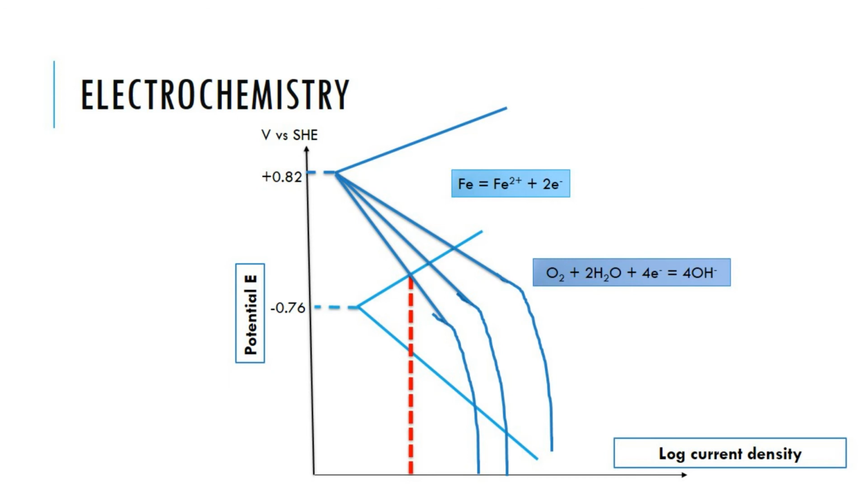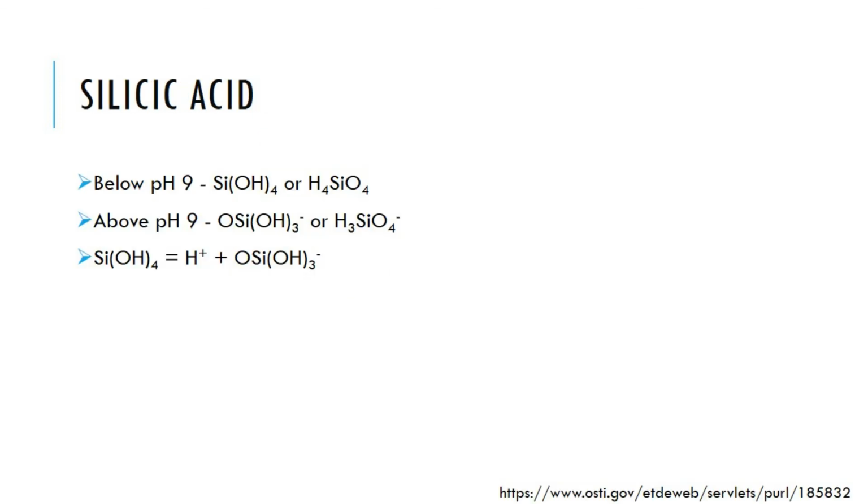Thus, sodium sulfide or the addition of oxygen scavengers can be related to the electrochemistry, and the proper selection of the amount can be done by analyzing the electrochemical nature and formulating the correct contents. Further, there is the concept of silicic acid. Now, this may not seem related to any other parameter, but in fact it is related to the pH. The pH of the boiler in the specifications is 9 to 10.